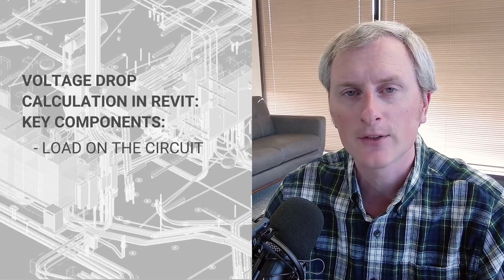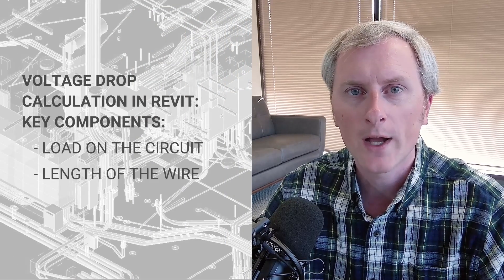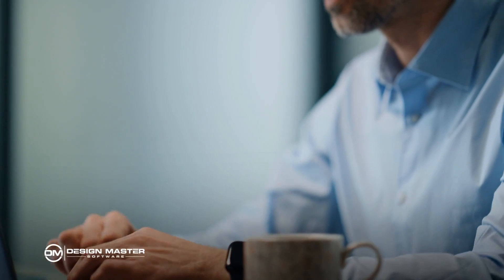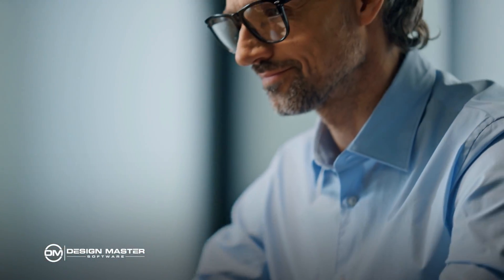Stay to the end of the video and I will show you a way that you can calculate voltage drop in Revit. The voltage drop calculation is a function of really three pieces you need to get from Revit: the load on the circuit, the length of the wire, and the impedance of the wire. Using those three pieces of information, you can calculate the voltage drop on the circuit. Let's take a look at how Revit handles all three of those.